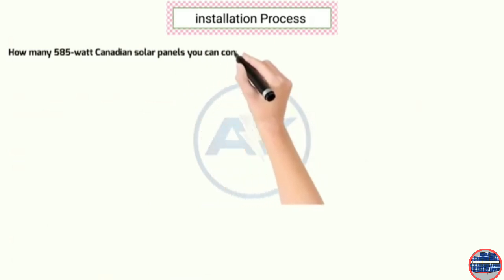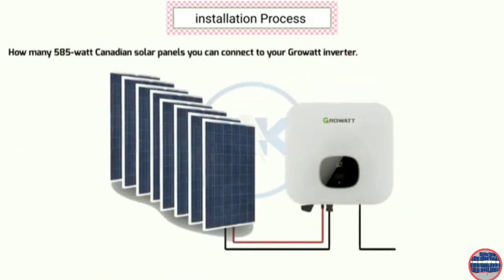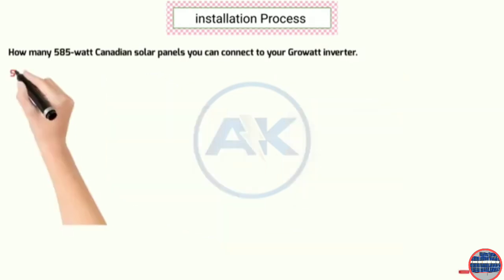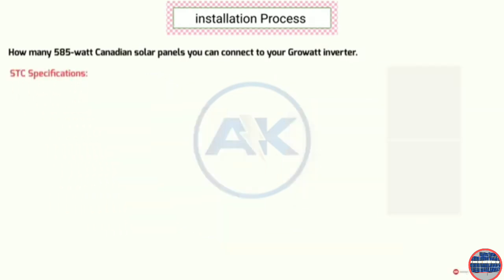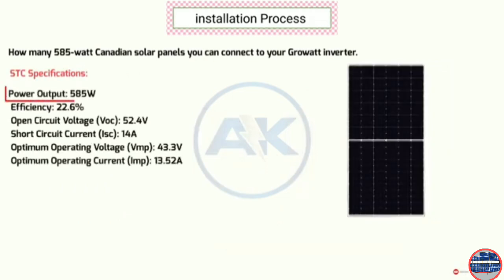Okay, let's figure out how many 585 watt Canadian Solar panels you can connect to your Growatt MOD 10000 KTL3-X inverter. Panel STC specifications: 580 watt Canadian Solar, power output 585 watt, efficiency 22.6%, open circuit voltage VOC 52.4 volts, short circuit current ISC 14 amperes, optimum operating voltage VMP 43.3 volts, optimum operating current IMP 13.52 amperes.